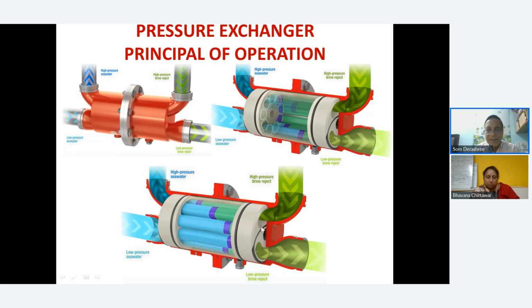So when this hole comes in front of here, see, this high pressure is pushing it here. When it comes here, this has already gone to the other side, where the suction part of the incoming pump is. So this is a continuous process of transferring low pressure fluid to the higher pressure side.